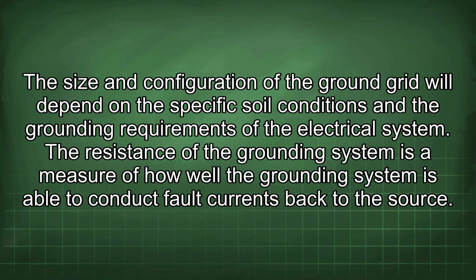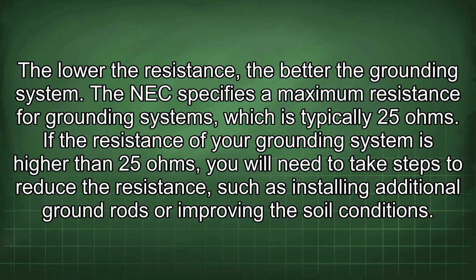The size and configuration of the ground grid will depend on the specific soil conditions and the grounding requirements of the electrical system. The resistance of the grounding system is a measure of how well the grounding system is able to conduct fault currents back to the source. The lower the resistance, the better the grounding system. The NEC specifies a maximum resistance for grounding systems, which is typically 25 ohms. If the resistance of your grounding system is higher than 25 ohms, you will need to take steps to reduce the resistance, such as installing additional ground rods or improving the soil conditions.